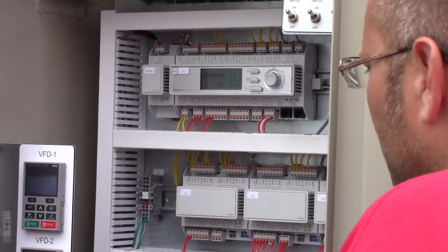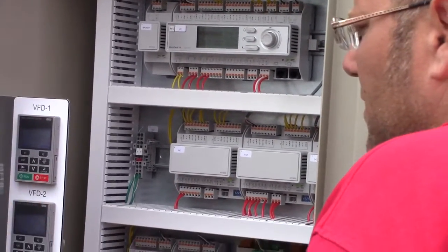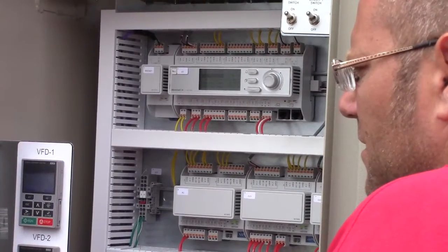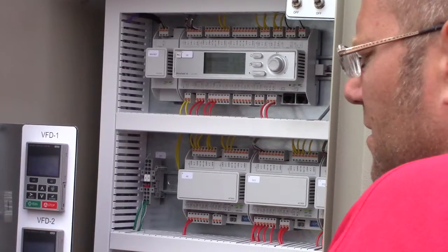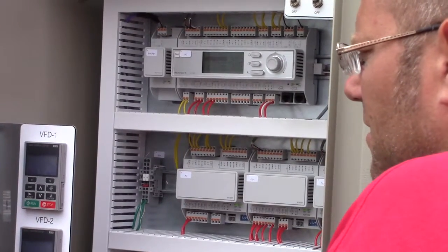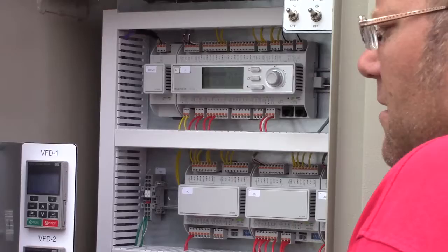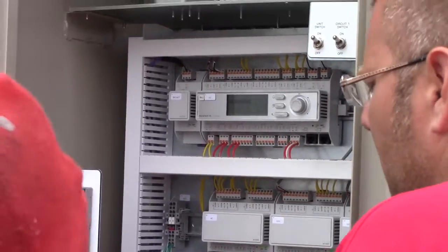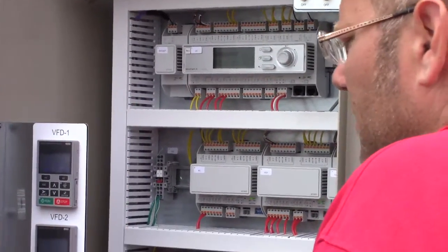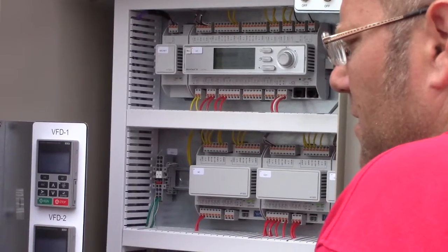And the nice thing is I can show you there is the ability to put it in a manual mode and you can fully control all the different points. So if you wanted to shut the chiller down completely and run through outputs, see the fans work, see the valve drives, see that all your solenoid coils bang on when you tell them to, that kind of thing.